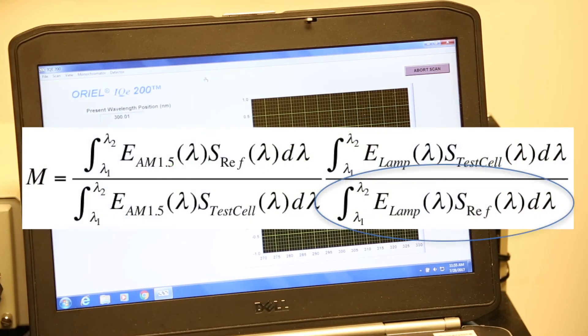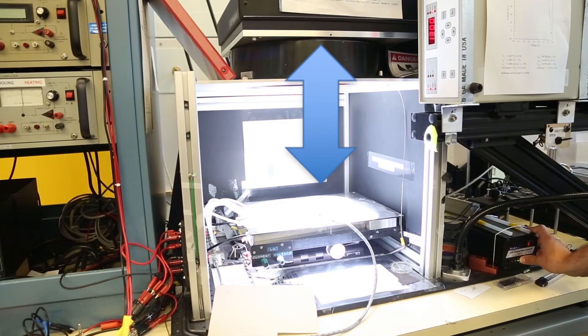Next, measure the short circuit current of the reference cell with the light source you have. If it doesn't match with the ISC obtained in step one, adjust the intensity of your source. You can do this by adjusting the distance between the source and the sample.